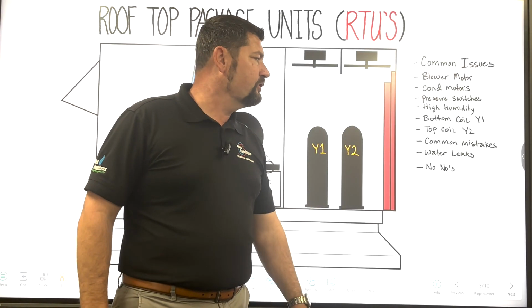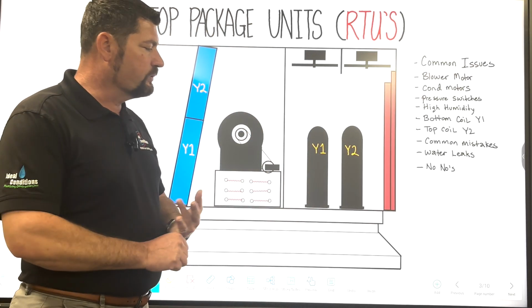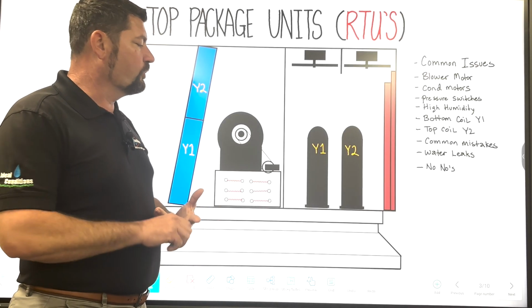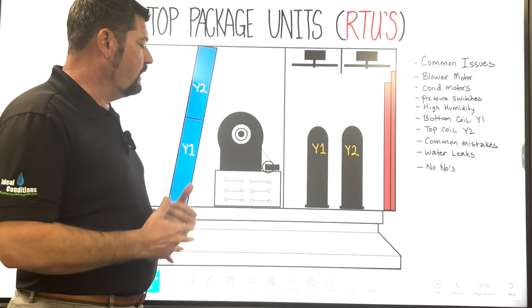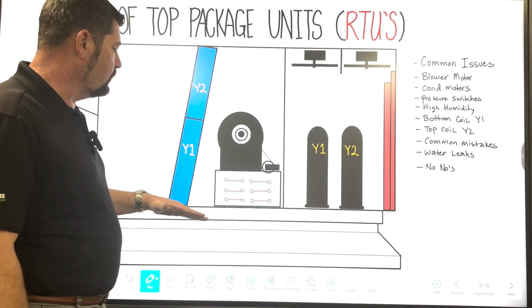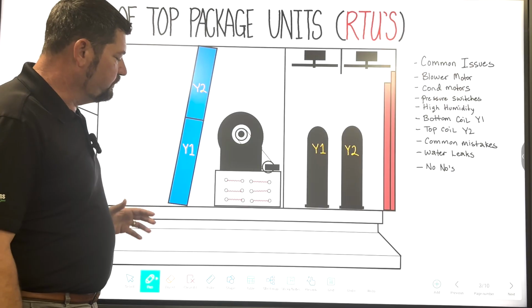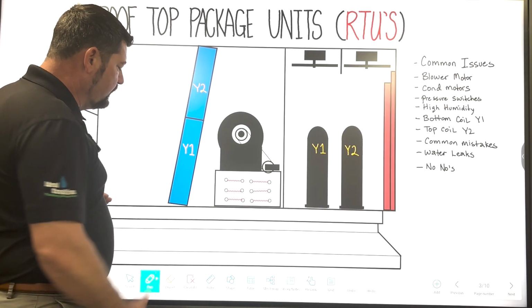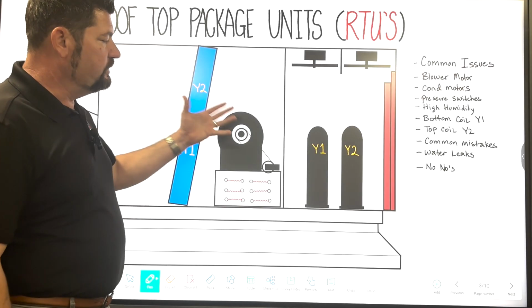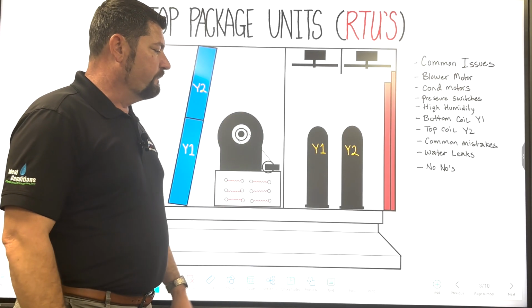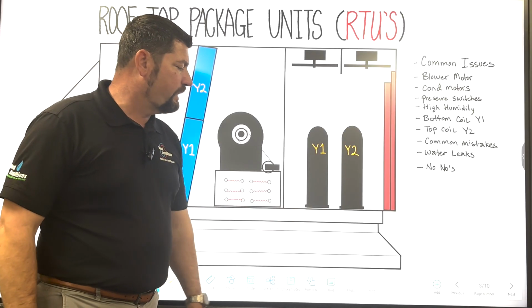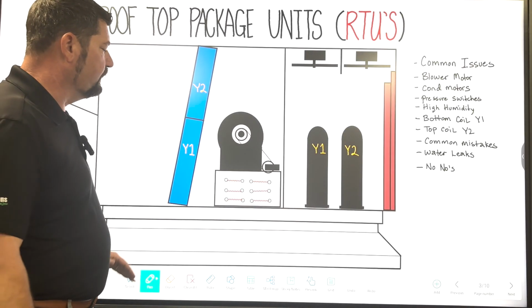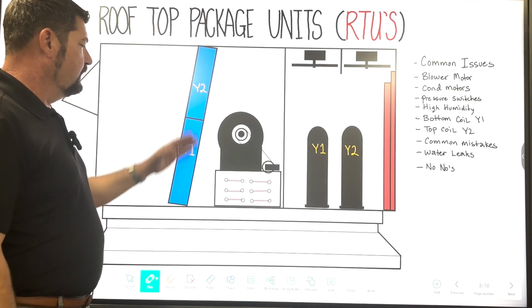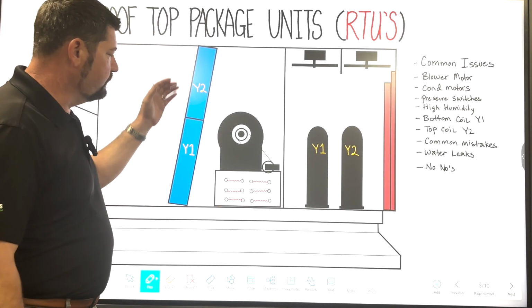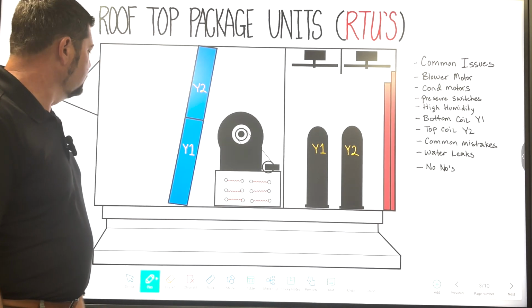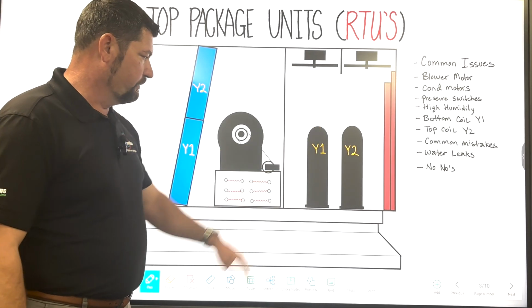We're going to go over common issues. Common issues on these are refrigerant leaks, dirty coils, corroded coils, installation errors where maybe when the package unit was installed, they didn't line up the supply and return air plenum correctly, so they could be backwards or they could be partially covered up. Sometimes these units wind up getting upsized due to the demand for more cooling capacity, and these plenums do not get upsized with them, so we experience a lot of flood back on these compressors where liquid refrigerant migrates back to the suction on the compressor, losing oil, killing compressors.